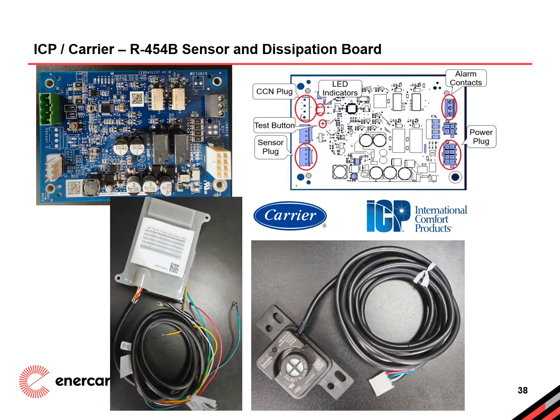Here's how the sensor works. When it detects a refrigerant concentration at approximately 20% of the lower flammability limit, it takes action to ensure safety. The outdoor unit and heating system will be powered off, while the indoor fan is brought on to dissipate the leak safely. To simplify installation, the dissipation wiring harness includes clear, labeled connections. Even with these features, always follow the manufacturer's provided installation and wiring diagrams from Carrier and ICP. Adhering to these guidelines ensures a safe, effective setup. It's all about making safety and performance our top priorities.